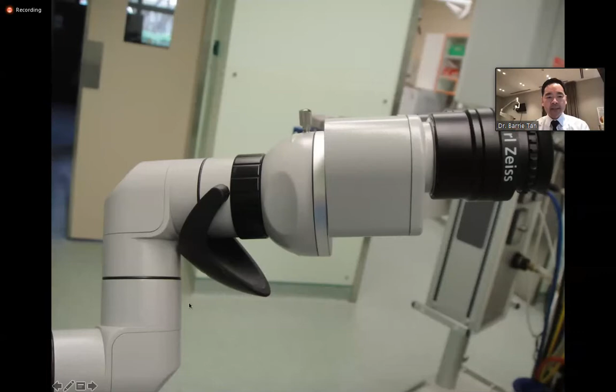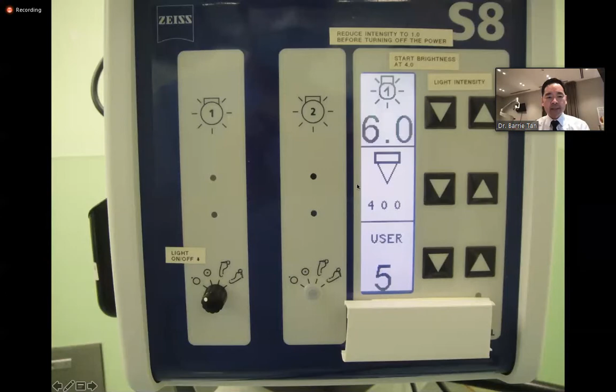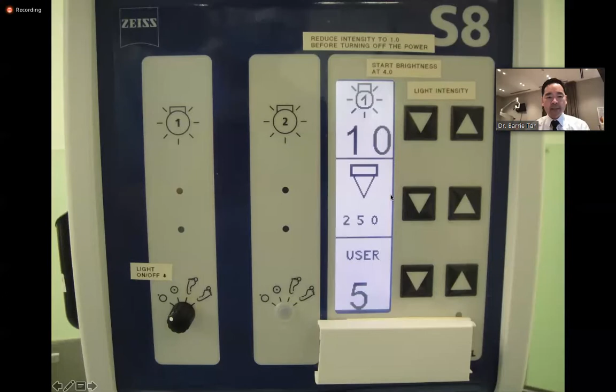And the controls of many of these electronically powered microscopes nowadays will have different settings. This references the focal length and the light intensity. In this setting, always check before you use the microscope whether it is correctly positioned for an otology case. Here, you can tell that from the focal length of 400 millimeters, this is incorrect. This is actually meant for larynx work. So you need to reduce it down to 250 millimeters or less for otology operations. And for the light intensity, my personal preference is to increase the light to its maximum capacity.